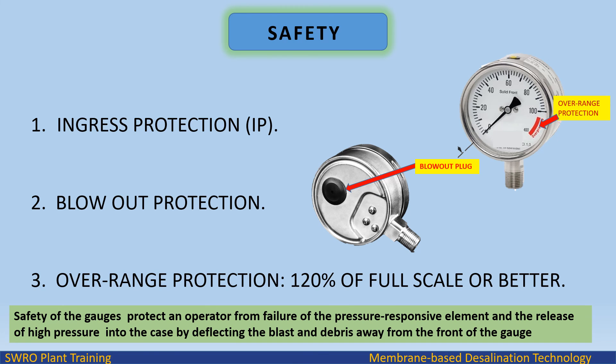Safety: Safety considerations include ingress protection (IP rating), blowout protection, and overrange protection (120% of full scale or better). Safety features protect the operator from failure of the pressure-responsive element and the release of high pressure into the case by deflecting the blast and debris away from the front of the gauge.